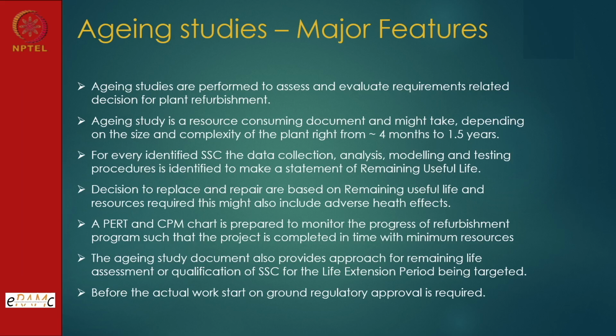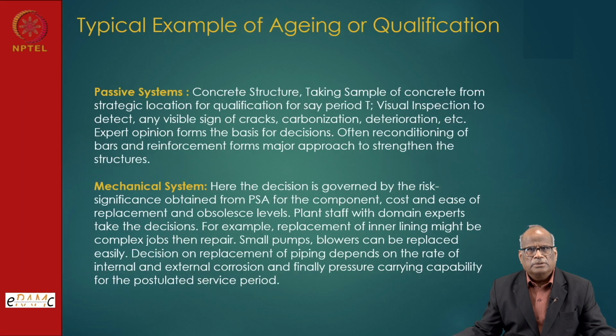Then there is the question of how much time is granted. Let us say a regulator agrees to 10 years, with an interval revisit to the regulator regarding performance of the system, and you get 10 years, which happened in our case study. For passive systems and mechanical qualification, as I told you, take a sample and understand the deterioration. For a mechanical component, you see the performance, and qualification is done on that basis. Let us say there is a piping: how much remaining thickness is left, and is it sufficient? Based on previous data, it can go for another 10-15 years, or replacement is easier, and those kinds of decisions can be taken.